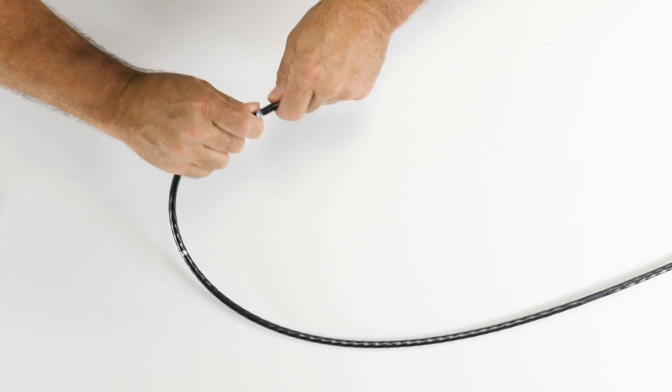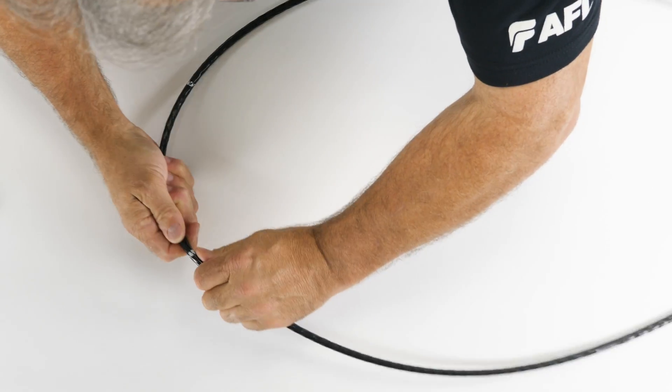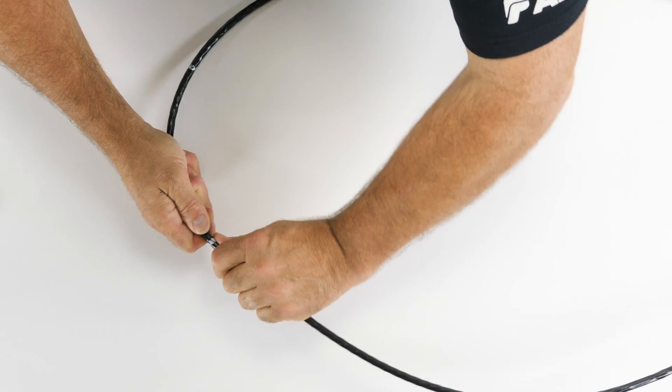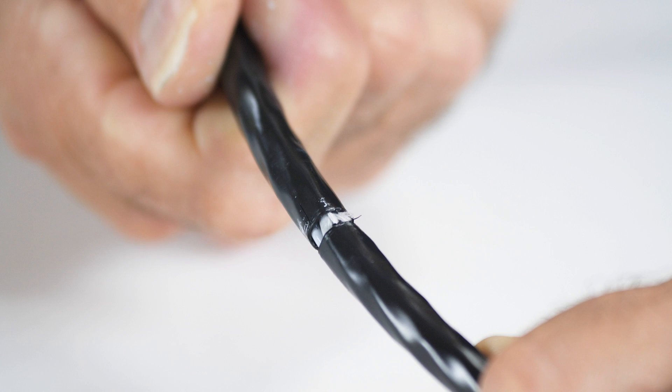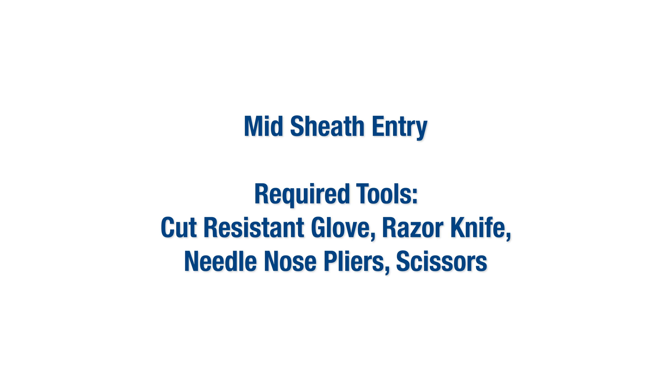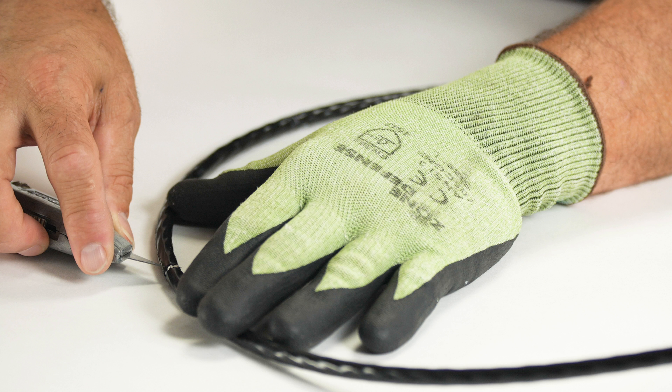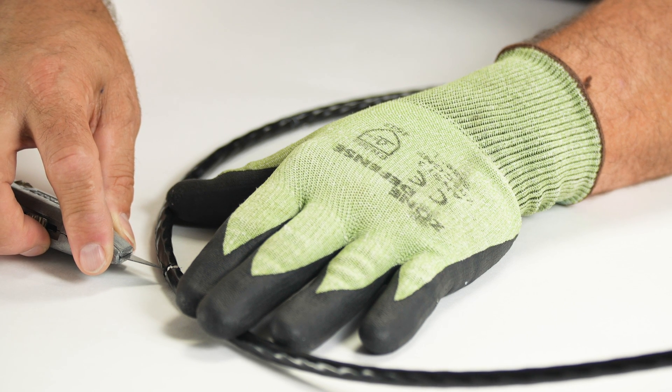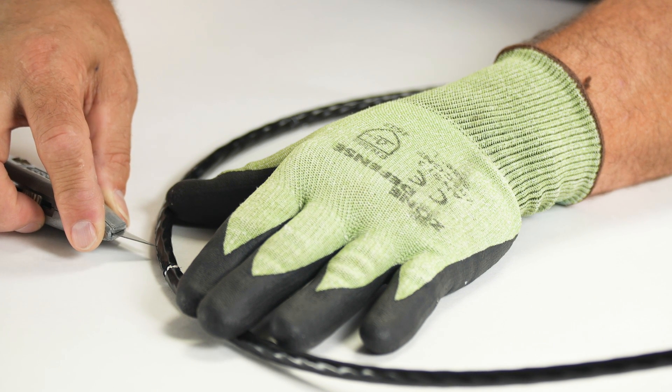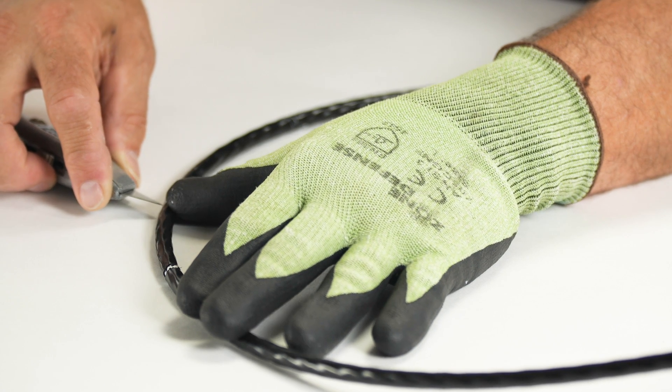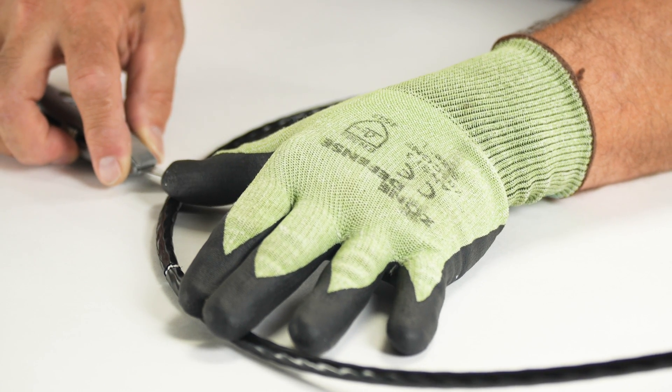Slightly bend the outer jacket at each of the ring-cut locations. This process will separate the jacket and allow the ripcord locations to be visually identified. Place the razor knife on the 8-inch portion of the jacket surface. Be sure that the ripcords under the jacket are located 90 degrees away from the scoring location. Carefully score the 8-inch surface of the jacket without penetrating completely through the material.